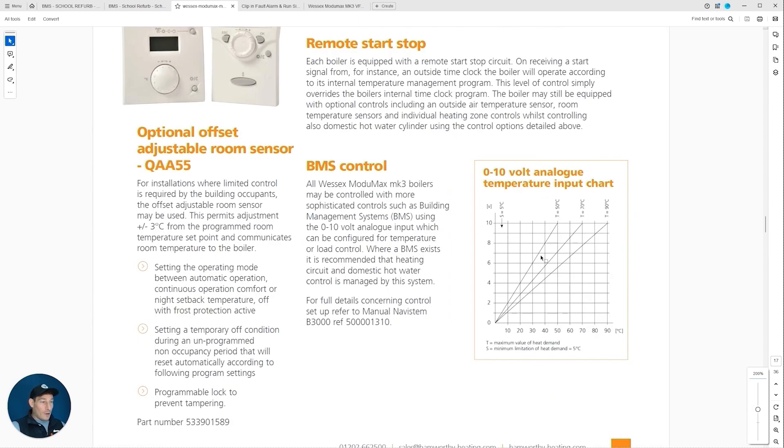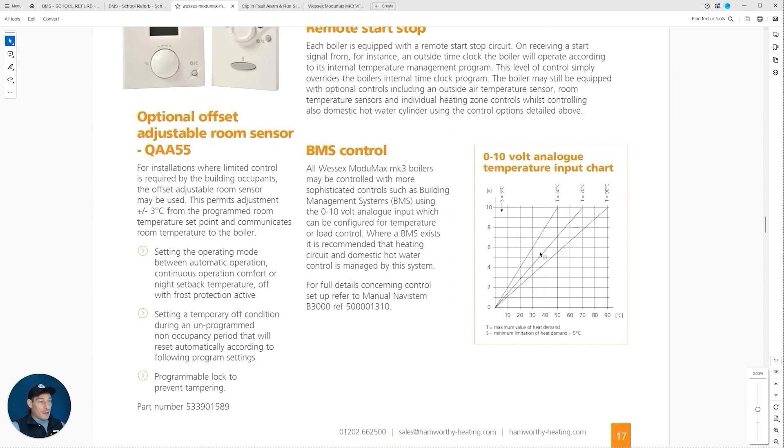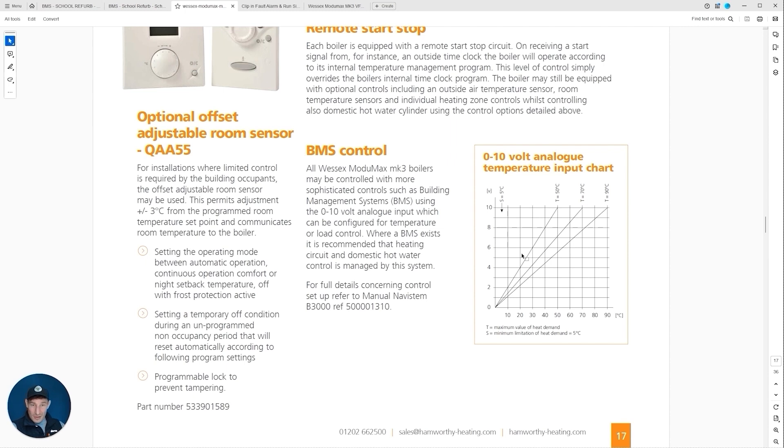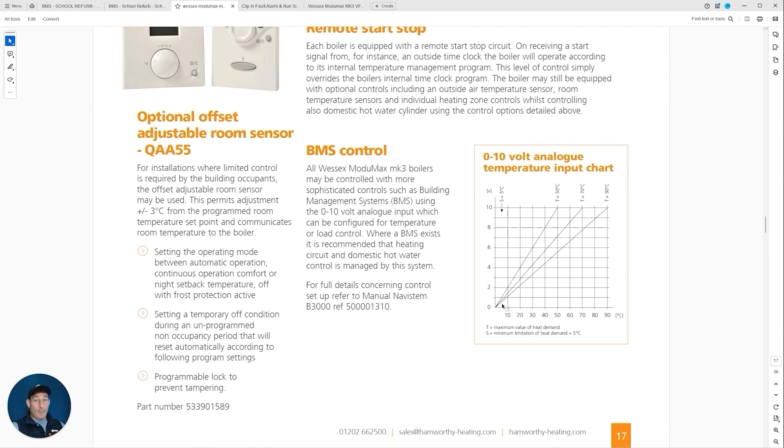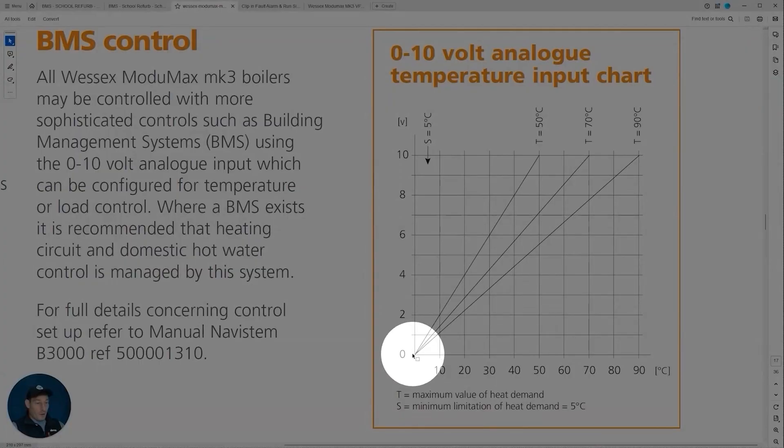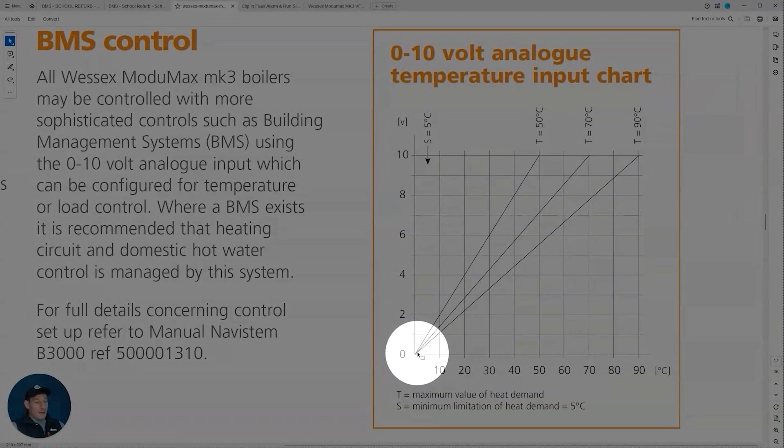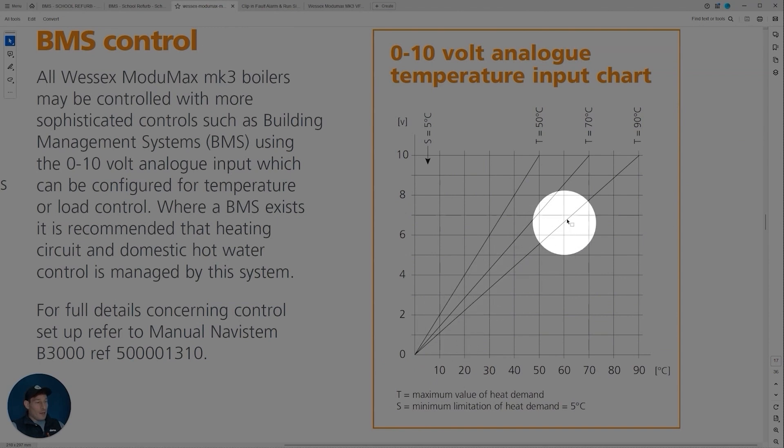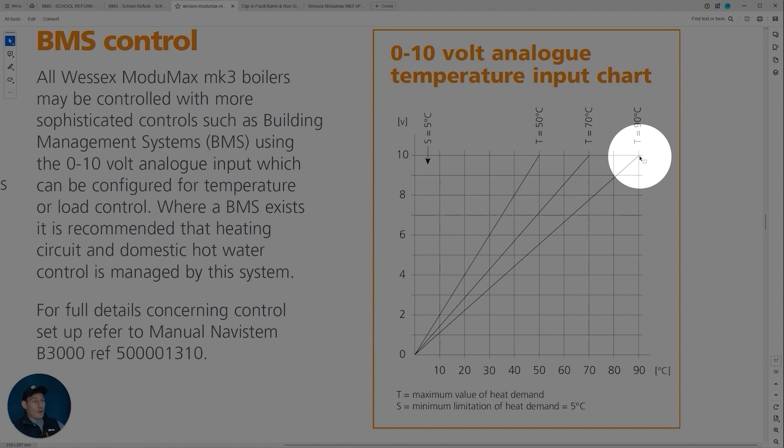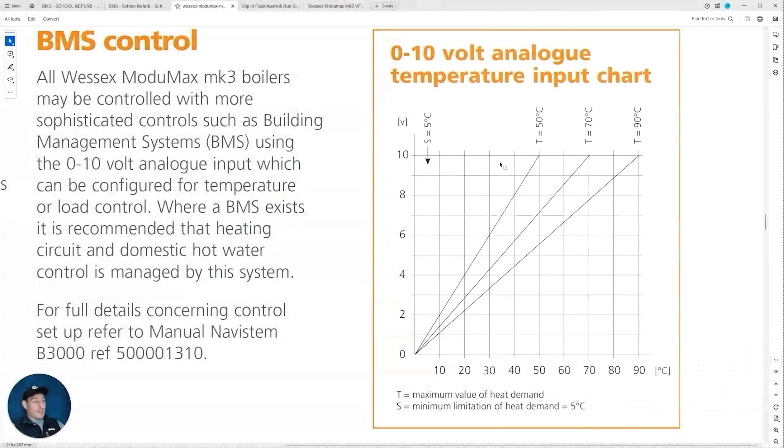If you have a look at this 0 to 10 volt analog temperature input chart—we're going to get into more details in a second but this is just for reference—this basically tells us what that 0 to 10 volt signal maps to in terms of temperature. Zero volts maps to zero degrees. Let's focus on this line here, we're using the boiler at max capacity, 90 degree heat, so the max control signal 10 volts we're mapping directly to 90 degrees Celsius.